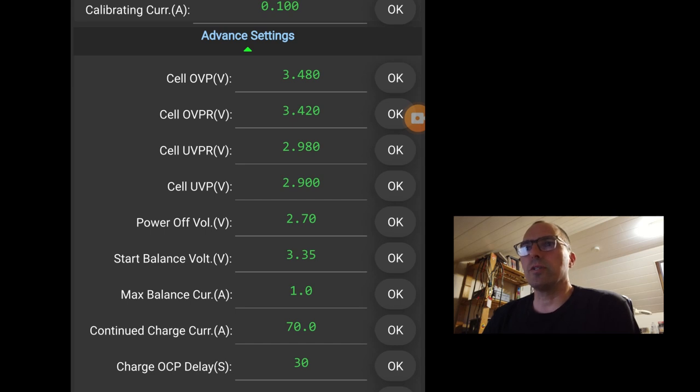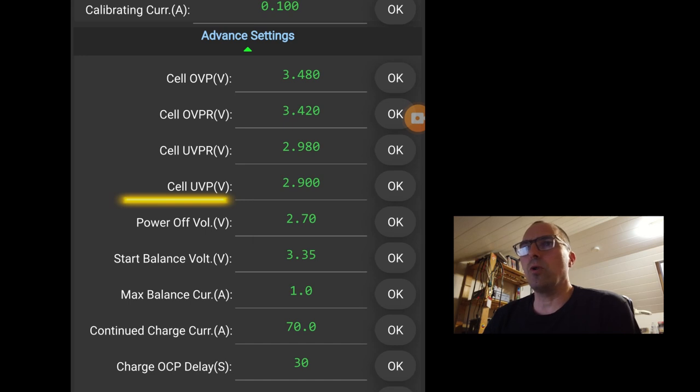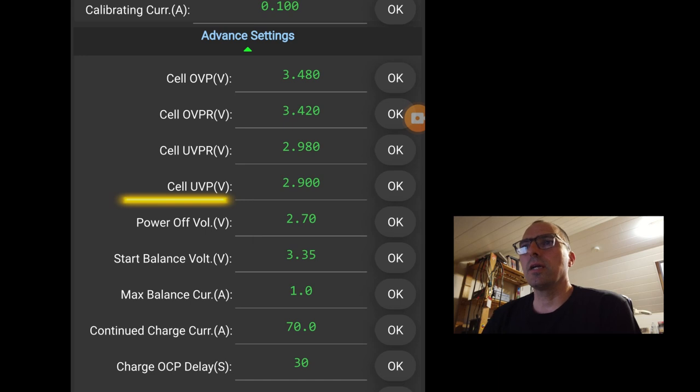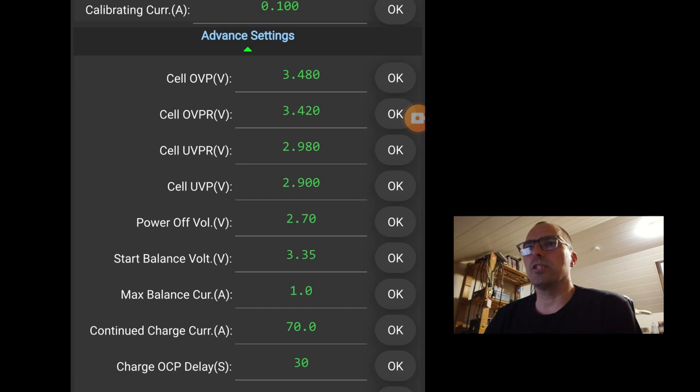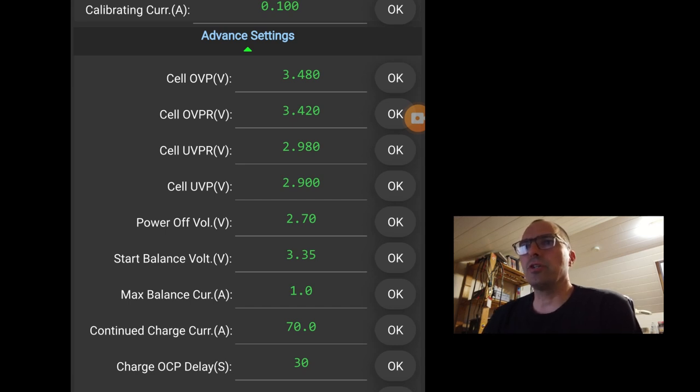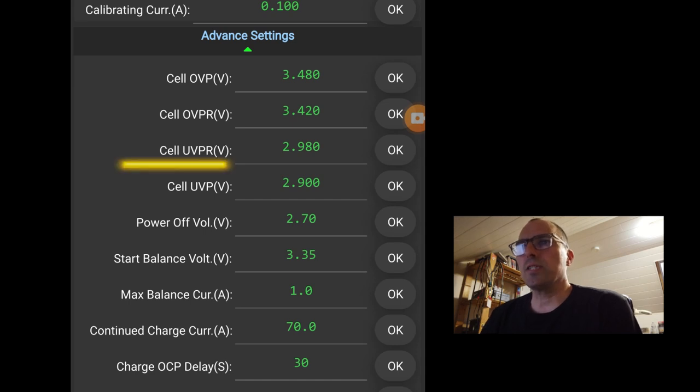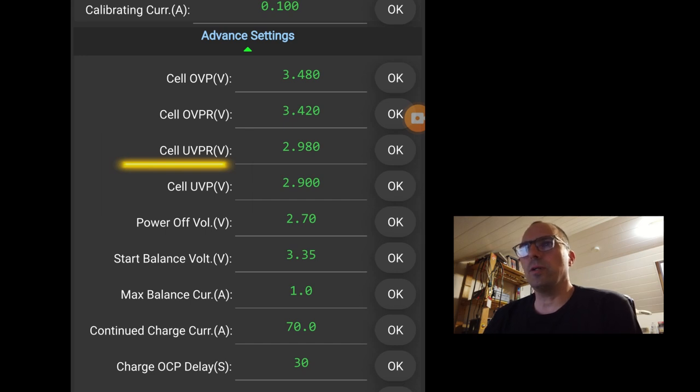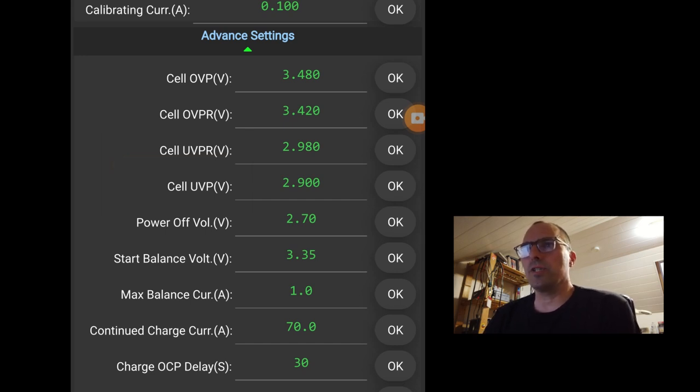Maybe we'll start with the cell under voltage protection. When one cell goes below 2.9 volts, the BMS will go in protection. It will prevent any discharge. Of course the charge and balance will work. Cell under voltage protection return. When the lowest cell hits again, the 2.98 volt. The BMS will allow us again to discharge the battery.